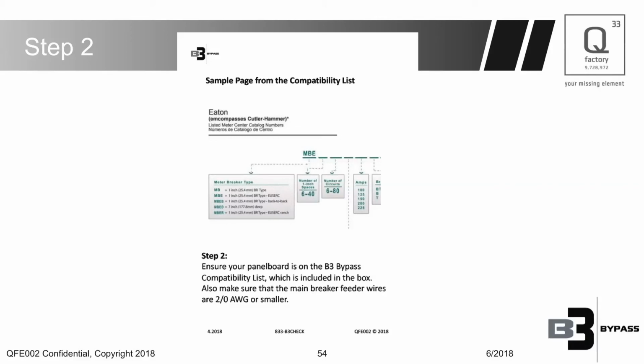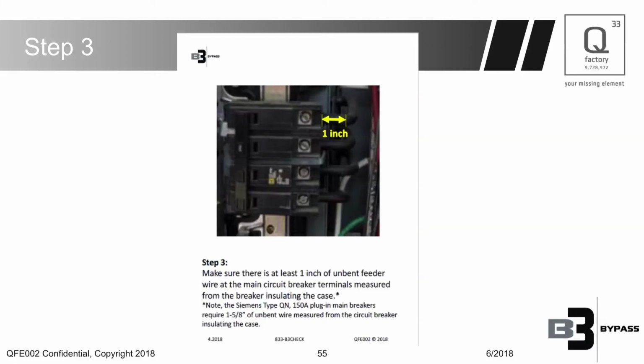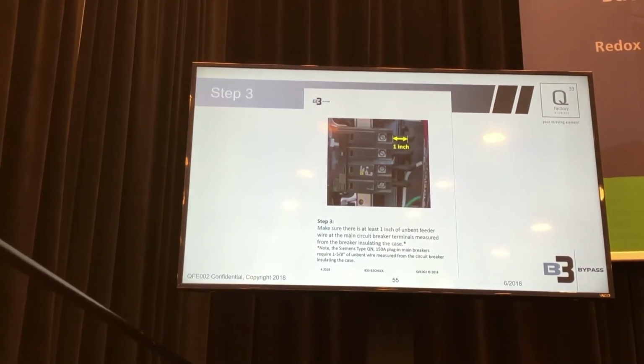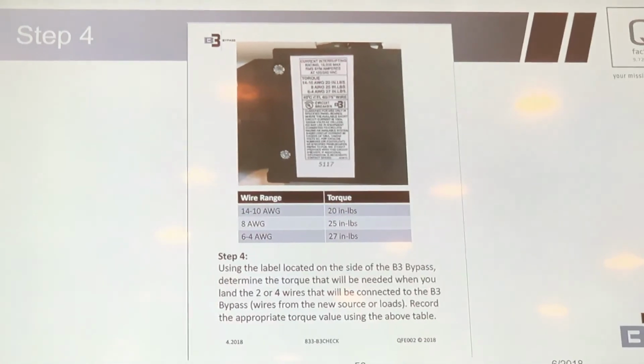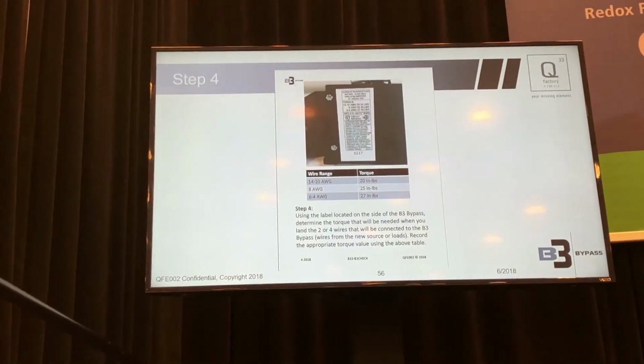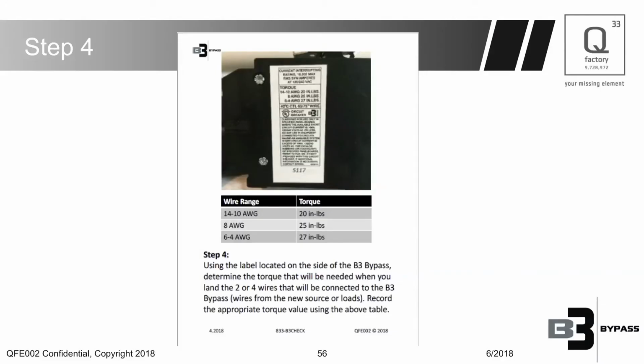So make sure the panel is on the compatibility list. This is redundant. If you email us, we'll give you the thumbs up, so you don't need to do this yourself. Just a quick reminder. Second reminder is we want to make sure there's enough unbent feeder wire so we can do a clean attachment here. So, third thing is on the side of the B3 is the torque specifications for the quad breaker. Okay, so based on the gauge wire you're going to use to land your new generation, we'll tell you what torque needs to be used. So here's the torque settings. Make sure you write that down, because once this is installed, there's a good chance you're not going to be able to see the side of this.